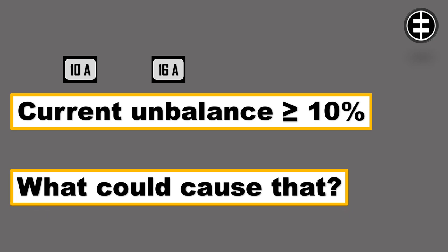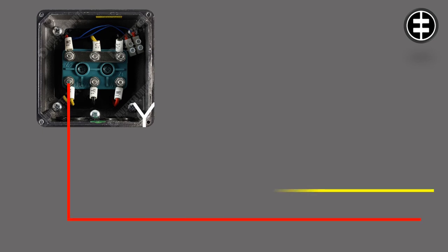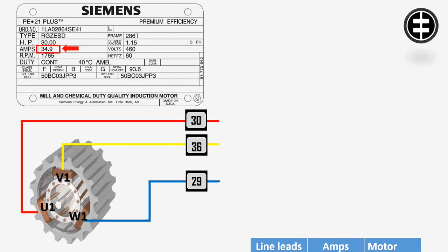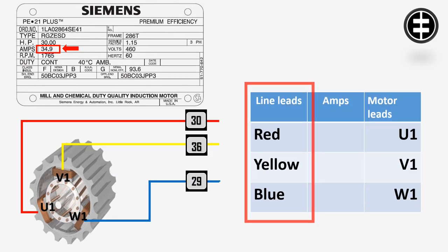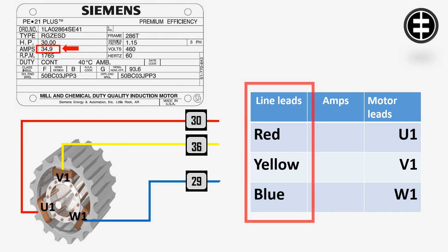In our case, red line lead is connected to U1, yellow line lead connected to V1, and blue line lead connected to W1. Draw this table: on one side will be the three line lead colors (red, yellow, and blue), on the other side the three motor leads (U1, V1, and W1).